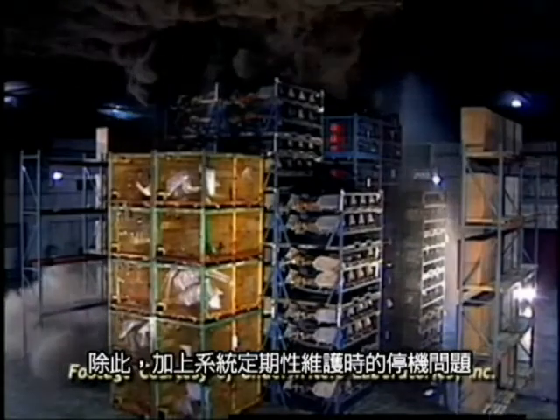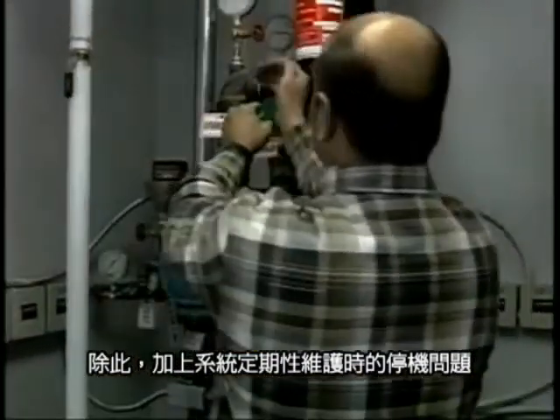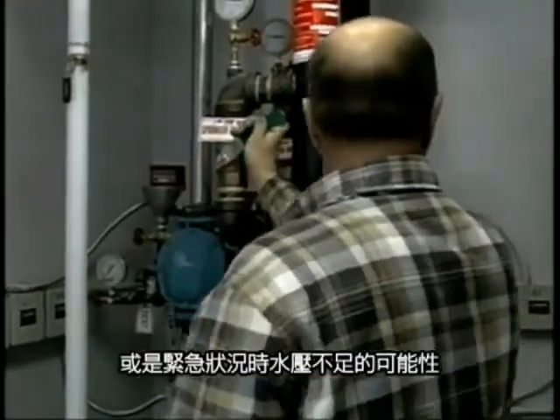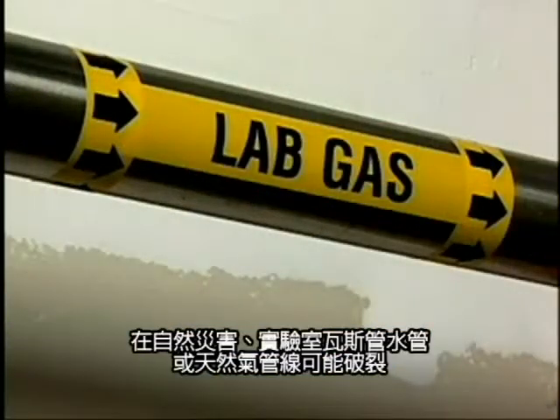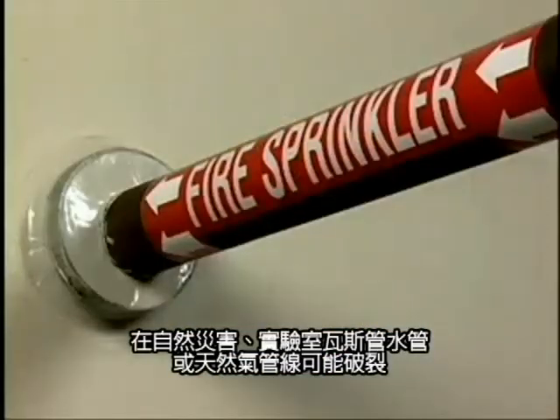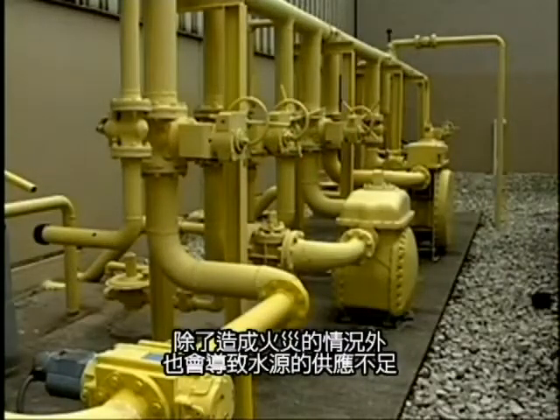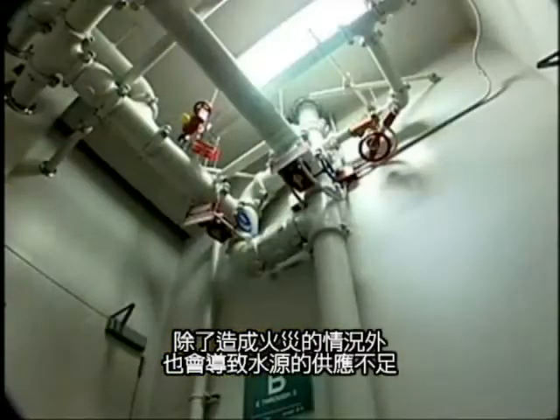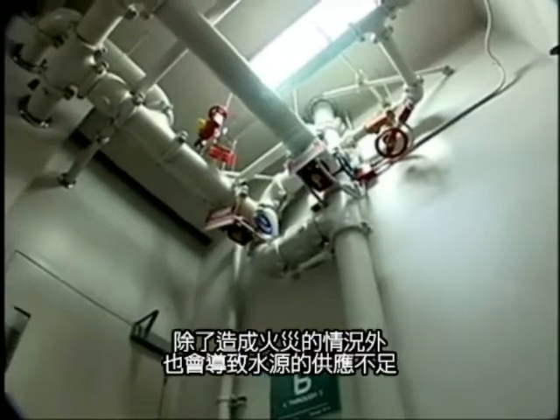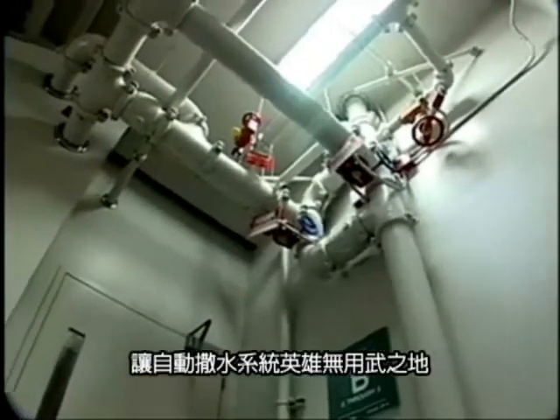Add to this the periodic downtime for system maintenance or the potential during an emergency for inadequate water pressure, and it becomes obvious that sprinklers are only one part of a complete fire protection plan. In a natural disaster, lab gas, water, and natural gas lines may be ruptured, triggering not only fires, but disrupting the supply of water, rendering an automatic sprinkler system useless.